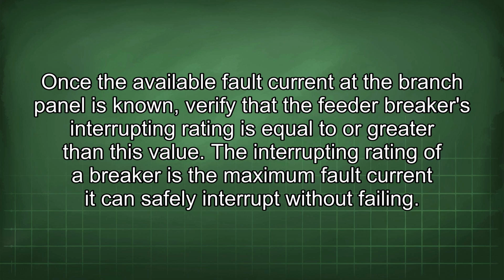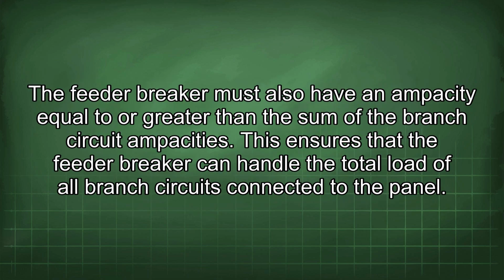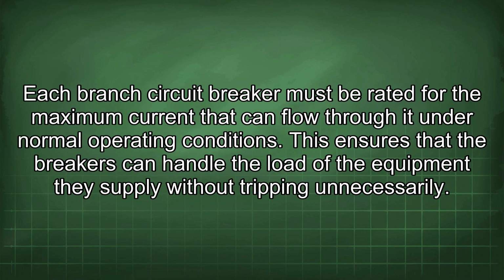The interrupting rating of a breaker is the maximum fault current it can safely interrupt without failing. The feeder breaker must also have an ampacity equal to or greater than the sum of the branch circuit ampacities. This ensures that the feeder breaker can handle the total load of all branch circuits connected to the panel. Each branch circuit breaker must be rated for the maximum current that can flow through it under normal operating conditions. This ensures that the breakers can handle the load of the equipment they supply without tripping unnecessarily.